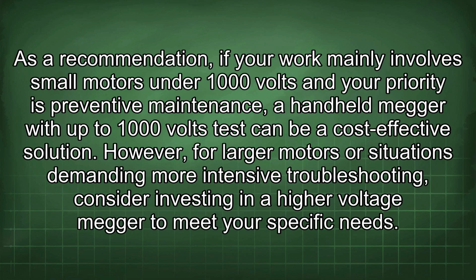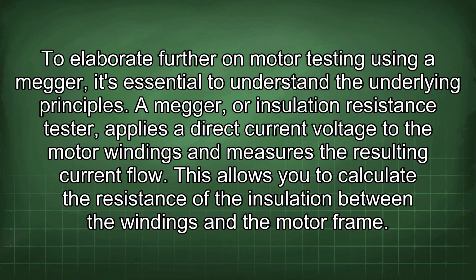As a recommendation, if your work mainly involves small motors under 1000 volts and your priority is preventive maintenance, a handheld Megger with up to 1000 volts test can be a cost-effective solution. However, for larger motors or situations demanding more intensive troubleshooting, consider investing in a higher voltage Megger to meet your specific needs. To elaborate further on motor testing using a Megger, it's essential to understand the underlying principles.